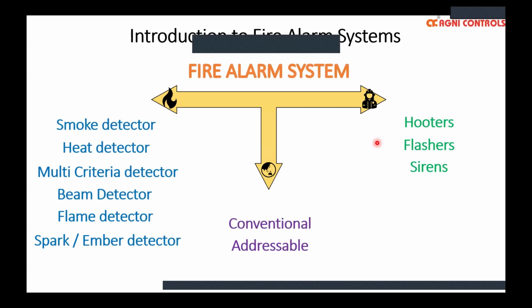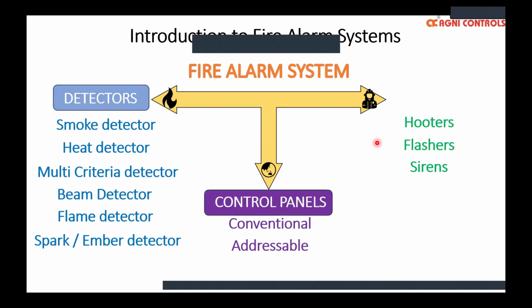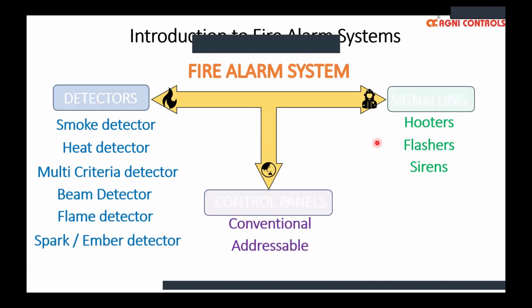So this is the basic fire alarm system, which all of you might know. It needs the detectors, first of all, the signal initiating devices, which are connected to a control panel, and signaling devices, which will give the outputs like alarms and operate gas suppression systems or other systems.